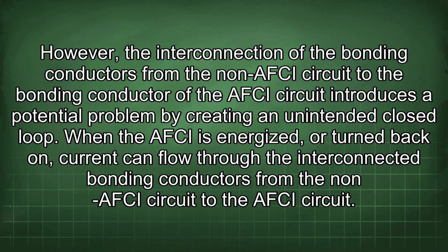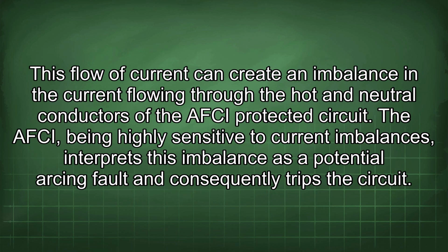When the AFCI is energized or turned back on, current can flow through the interconnected bonding conductors from the non-AFCI circuit to the AFCI circuit. This flow of current can create an imbalance in the current flowing through the hot and neutral conductors of the AFCI protected circuit.